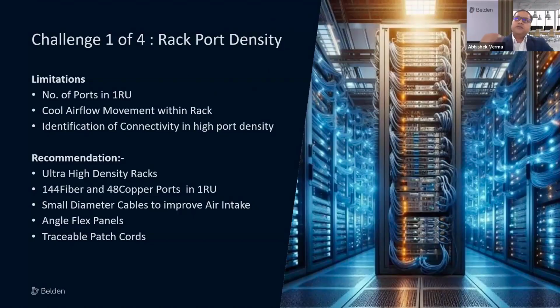So you can easily check which port is connected where. There are solutions for this in which, as per the standard rule, whenever you are putting a panel, there has to be another horizontal cable manager to manage the patching so that the dressing is better. For this, we generally go for an angular panel, which is V-shaped. Now, a V-shaped angular panel cannot fit in a closed rack because it hampers the door from closing.